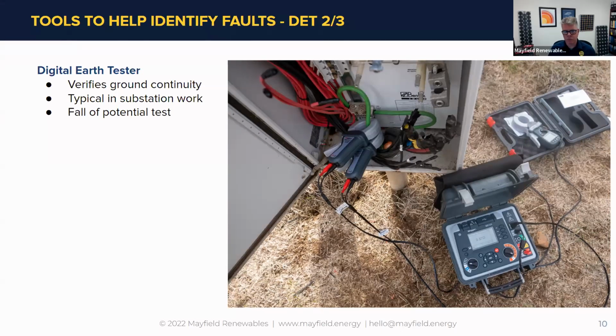Yeah, this is not something that I'm familiar with doing on smaller scale systems. As we get into these large systems, where there's a substation involved, this is where we're really starting to see these tests being performed, because it's a requirement and it's very often written into the spec, verifying the grounding system at the time of installation, and then annually, probably as a minimum, in order to maintain it. At a substation level, at medium voltage levels, if you have a problem with your grounding system, it can be catastrophic. So this is a really important thing that we're looking at there.